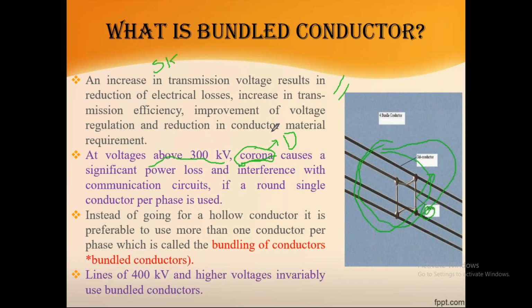So that's why this is the corona free conductor. Next one is, instead of using a hollow conductor, it is preferable to use more than one conductor per phase. So this is only one phase. For the remaining two phases, you can use this type of conductors, that is four. So this is for only one phase, single phase. In the single phase, we are using four subconductors as a bundle. Here one single conductor is called a subconductor, and these conductors are separated by spacers at equal distance. This type of bundle conductor we can use up to 400 kV, and higher voltages invariably use bundle conductors. So that is called bundle conductors, which we are using in the transmission lines.